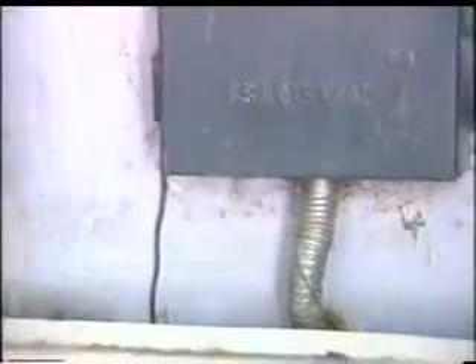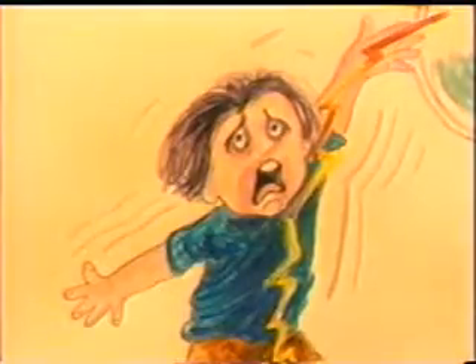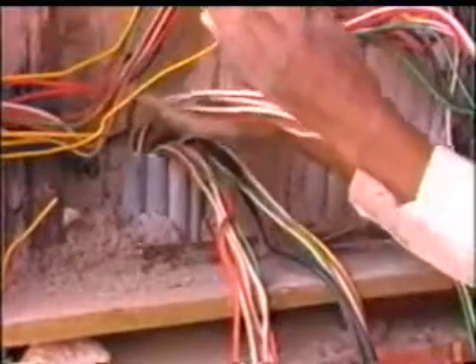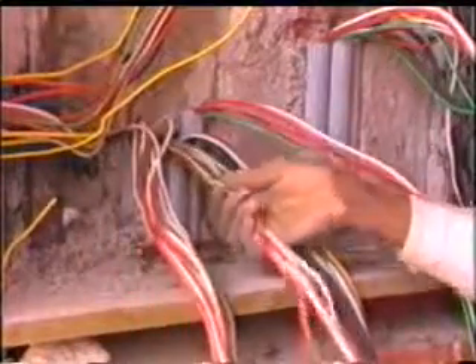Provision of earthing as per relevant electricity rules is essential to provide adequate safety to the users and the wiring system. Improper earthing may lead to fatal accident. Ensure earth wire runs along each circuit. Earth wires of all circuits must be effectively connected to the earth terminal on the main board.